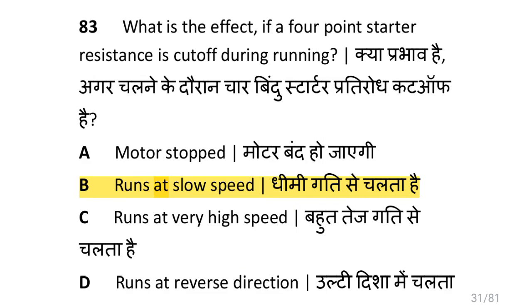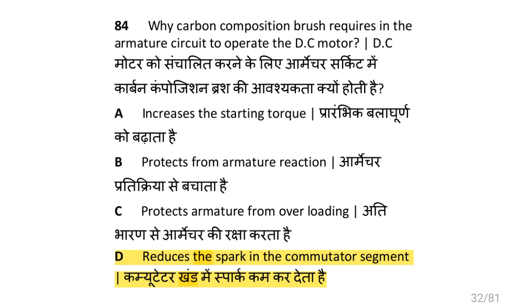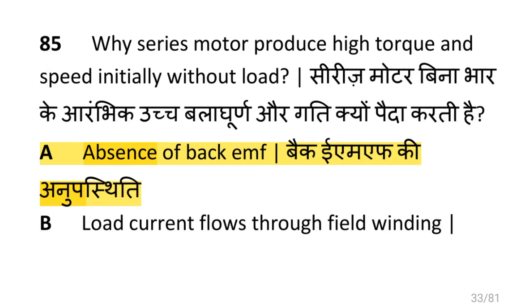What is the effect if a four point starter resistance is cut off during running? That is the motor runs at low speed. Why are carbon composition brushes required in the armature circuit to operate the DC motor? That is to reduce the sparking in the commutator segment. Why does a series motor produce high torque and speed initially without load? That is due to the absence of back EMF.